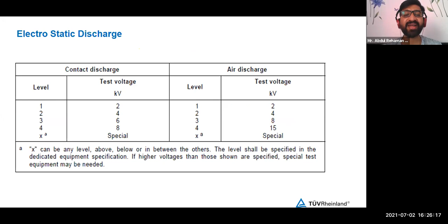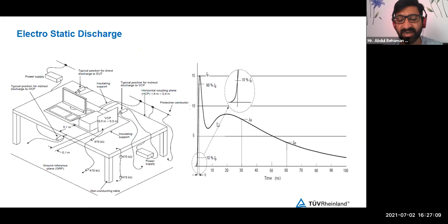These are the different levels defined in the standard for ESD. This is the table I was referring to. Here, this is the horizontal coupling plane, and this is the vertical coupling plane. This is the ESD gun through which the noise will be injected onto the product. So we have got different discharge networks for commercial products as well as for automotive products. Different networks are required for different sorts of standards. This is the extract from the standard about the test setup, where you have got different bleeder resistors for testing. This is a typical waveform for electrostatic discharge.